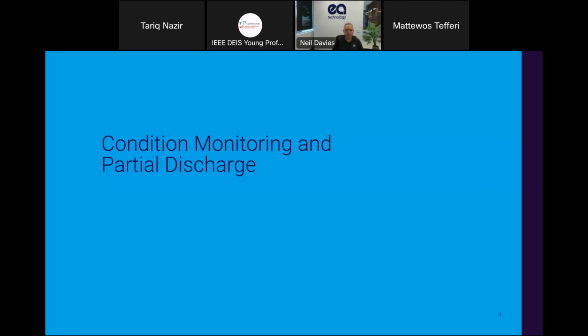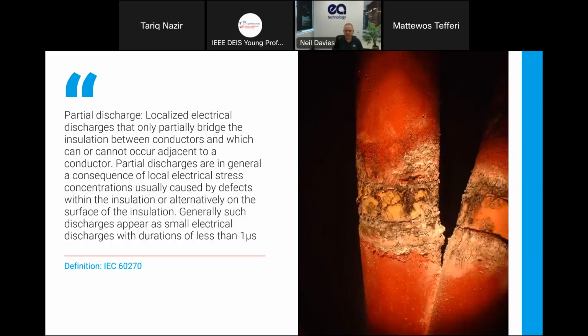So, very briefly, on condition monitoring and partial discharge. I'm sure, based on the audience, everybody's familiar with the definition of what partial discharge is. The IEC definition here, 60270. It's these small spikes of electrical discharges that bridge part of the insulation and start eroding the insulation until we get to the stage where the insulation cannot cope with the stresses and we get a full catastrophic breakdown. So these very short spikes are what we're really trying to detect.